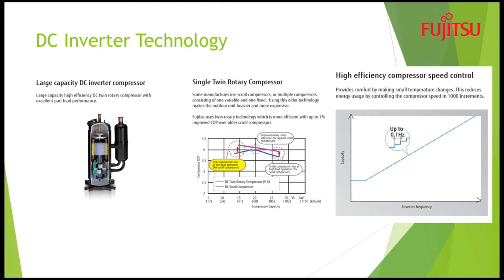Before, the compressors were AC and they were scroll type compressors. Here we have a DC power compressor. So we take the AC power, convert it to DC power through some complicated electronics, and then we provide a precise amount of pulses to that compressor to give us, here on the right hand picture, 1,000 steps. So instead of high, medium, low, now we have 1,000 steps in between to give us just the amount of frequency that we need to remove heat.